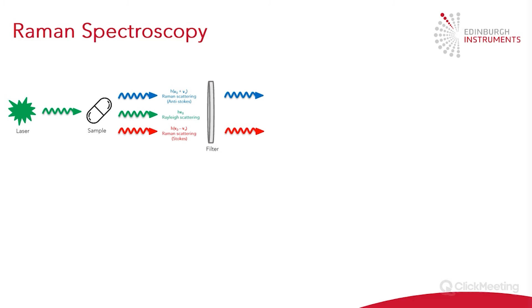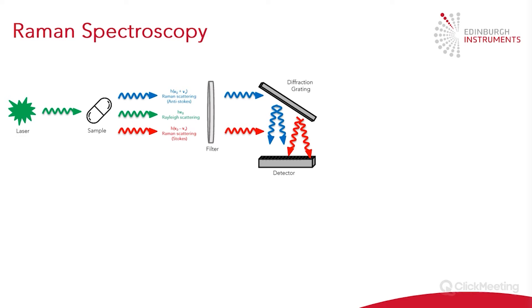Next, our light is directed onto a filter, and this filter is to remove the Rayleigh scattering that isn't of interest to us. We use either notch or edge filters to remove it, and then the Raman scatter is directed onto a diffraction grating. The grating splits the light into its constituent wavelengths, and this is then focused onto a detector.